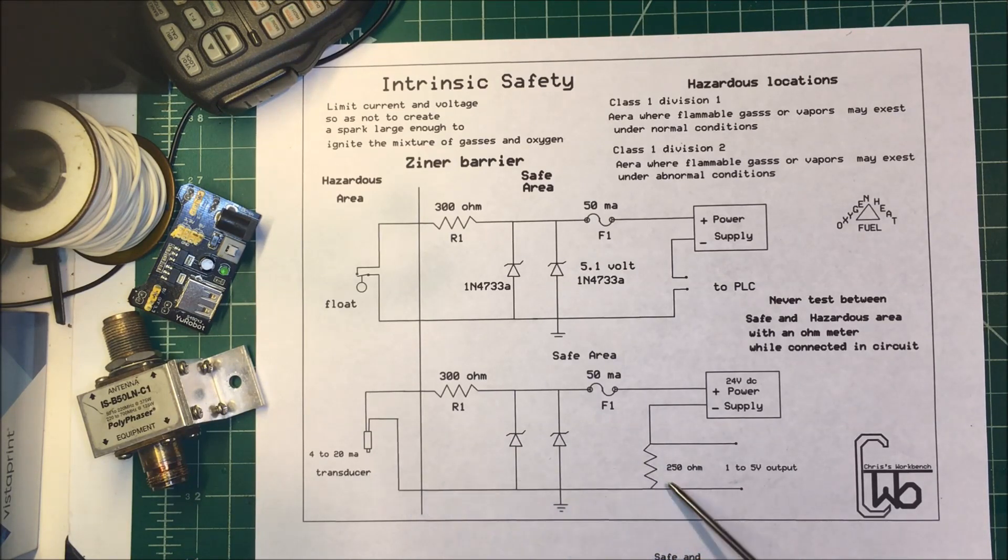Now if we put 4 milliamps across a 250 ohm resistor we get 1 volt out, and if we put 20 milliamps across that resistor we'll get 5 volts out. So we use this 1 to 5 volt signal and put that into our PLC to control whatever we're controlling for our pressure.